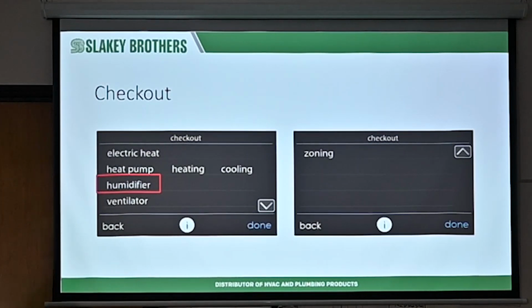It'll come on. Your pressure will be all crazy because it's really warm inside and really warm outside. Your low side will be really higher than normal, and your high side will be higher than normal. That's okay, you're just testing. You're just going to make sure it works really quick. If you don't want to, you don't have to. If you test the air conditioner, theoretically that tells us the heat pump should work.